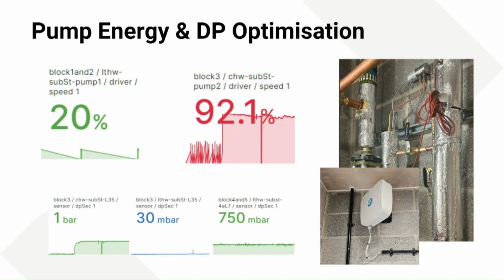So this is sites we're working on - we're looking at the visibility of the pump controls. This is quite typical when you look at pump controls, you see that they do weird stuff. If you look at pressure sensor data, you understand why. Adding visibility to DP sensors and pump speeds is really easy, and it's very low hanging fruit.